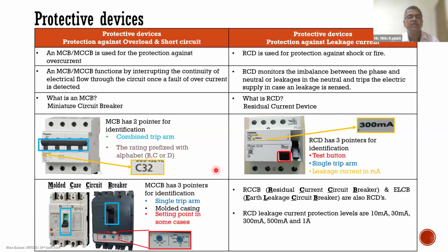Now let us look at the protective device types. On the left-hand side here, you have the MCBs or the MCCBs. MCBs are miniature circuit breakers and MCCBs are molded case circuit breakers. How are these identified? You have the type mentioned here. It is a type C here, and this is the rated current of the MCB. In case of an MCCB, you have a single trip arm, and in some cases you also have setting points where you can adjust the values on the side.